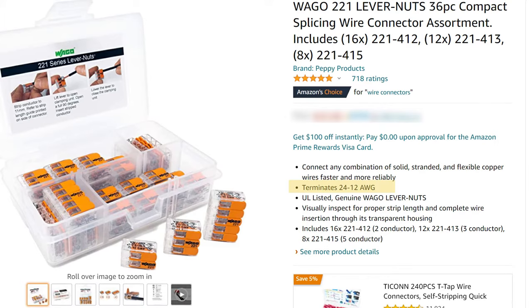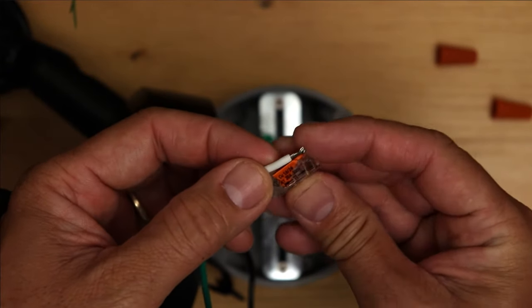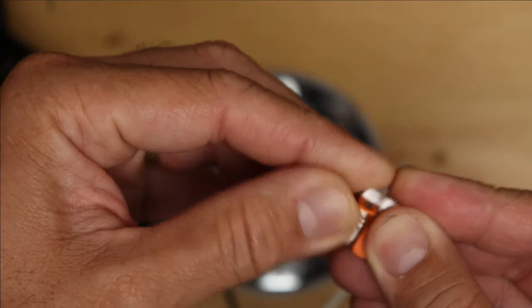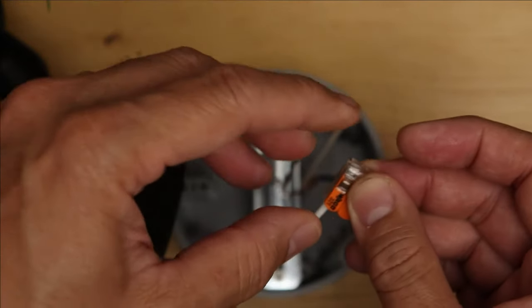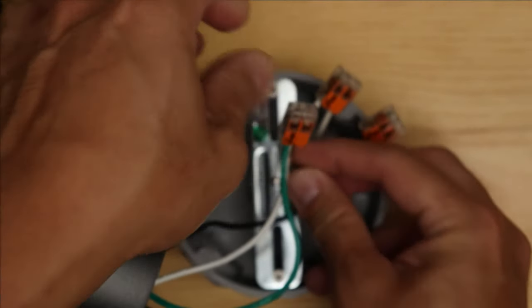With the WAGO connectors, it can connect from 24 gauge up to 12 gauge wires and it can be solid, stranded and flexible copper wires. Connecting wires using the WAGO connectors is easy and is faster. Strip the wires to 11 millimeters — there is a guide on the side of the connector — just flip the lever up, slide the wire in, and flip the lever down. That easy. And do the same thing on the other wire or wires that you want to connect.